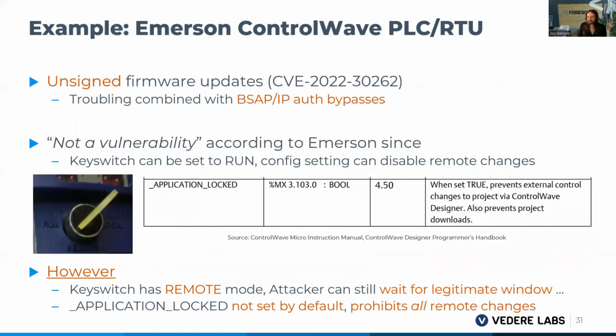An example of this is the Emerson ControlWave PLC that we talked about a little bit earlier. Firmware updates here are, again, unsigned, and this is especially troubling given that they happen over this BSAP IP protocol we talked about, with all its authentication issues. Again, unfortunately, Emerson didn't consider this a vulnerability either, because they said there is a key switch that can be set to run mode. There's a configuration setting which can be set to disable any remote changes. The problem is that this key switch also has a remote mode, and that essentially means that this barrier of defense puts all the onus on risk control on the discipline of the engineers. Because if they screw up there and leave it in remote mode, you don't have proper authentication to prevent the downloads. You don't have firmware signing to prevent malicious firmware.